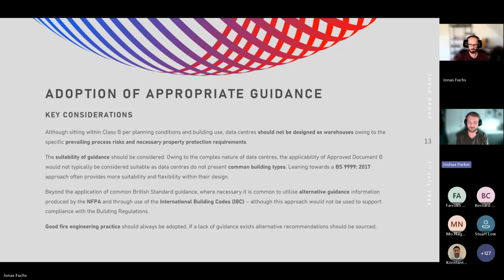But often what we find is the operators of these data centers do seek for us as fire engineers to use alternative guidance, just by virtue of where the operators are often from, which sees the adoption more often than not of the NFPA suite of documents and the IBC to support any BS 9999 design. Obviously using the NFPA and IBC isn't a means to demonstrate compliance with the building regulations. We still rely on 9999 for that, but it helps to supplement specific systems that may be adopted within that building. Above all, good fire engineering practice should be adopted. If a lack of guidance exists, there will be an answer somewhere, and it's finding that answer through either the NFPA suite of information, the IBC, or elsewhere within the British Standard suite of documents to find the most appropriate and tailored solution to the prevailing risk.